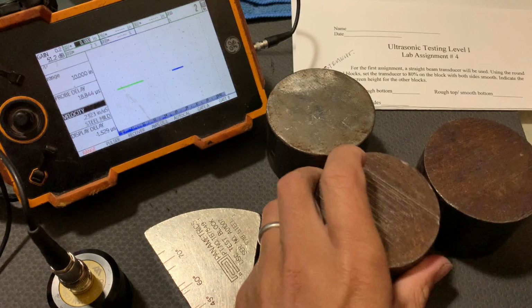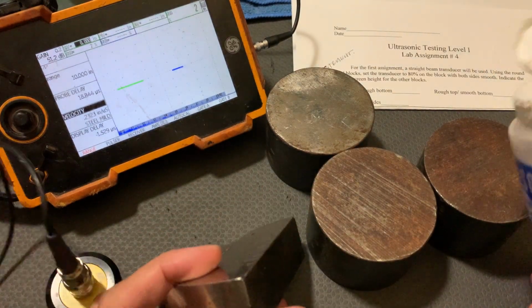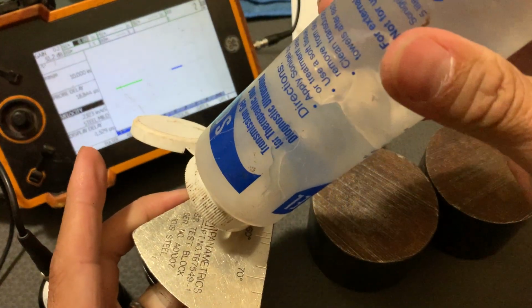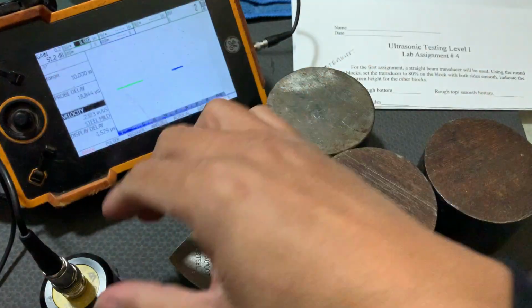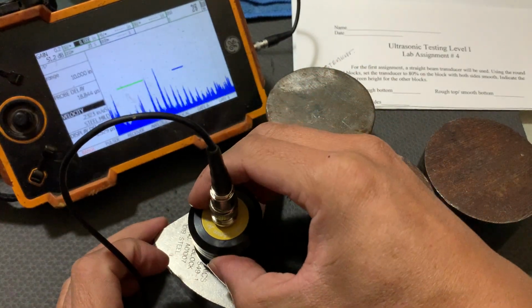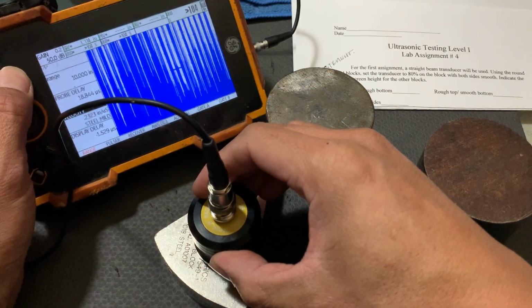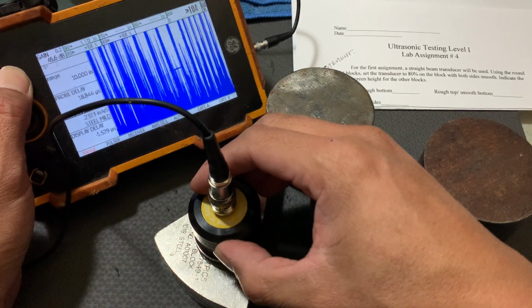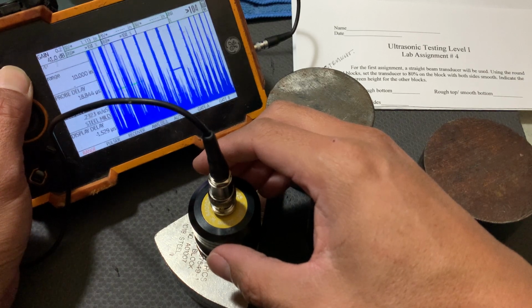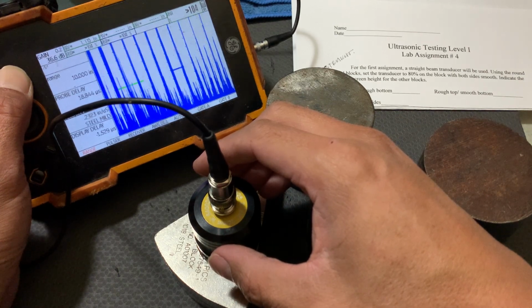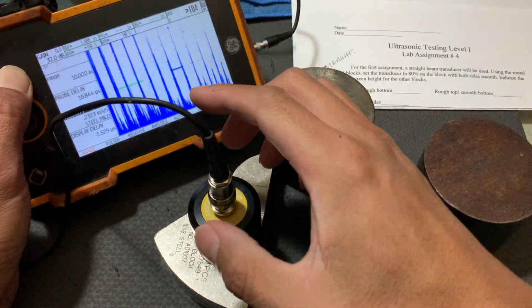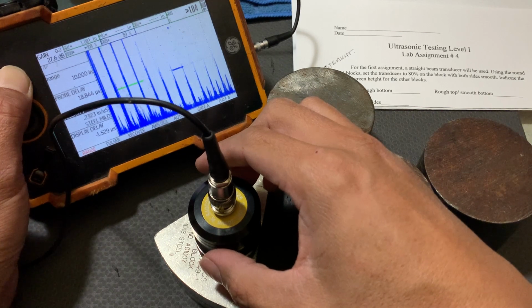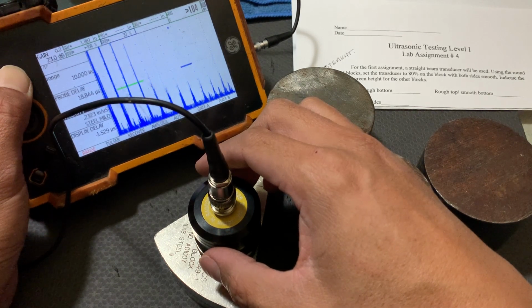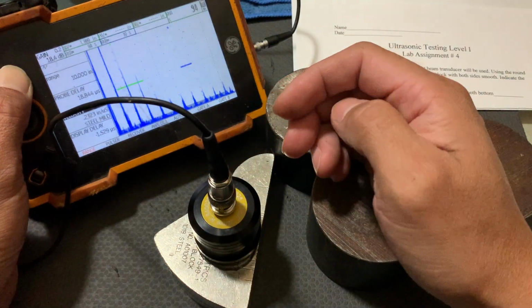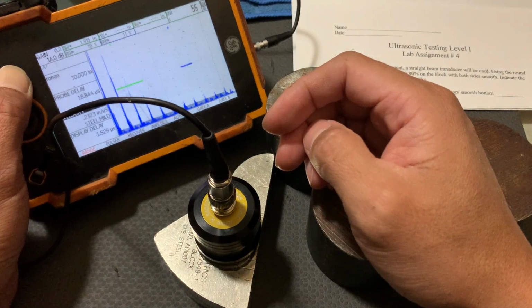Using regular couplant. Got a DSC block. Keep in mind of the side cut there. Dab a little bit of couplant on there. Got my transducer hooked up on my cable. Put that on there. Oh, way too much gain. Turn that down a bit. As you see, I got a 10-inch range on the screen. Just turn it down. I want to get it to 80% screen height on the first back reflection.